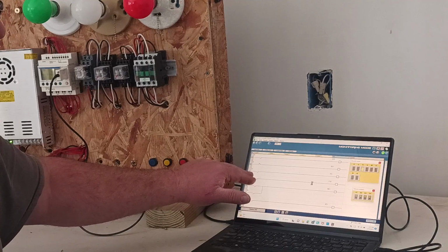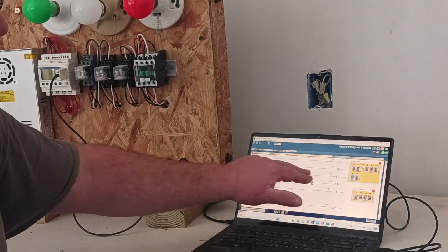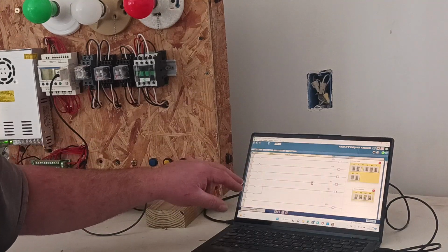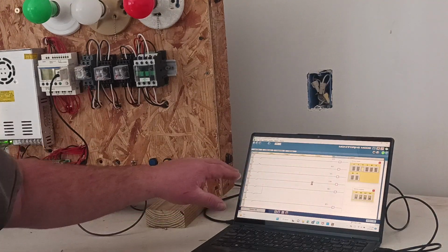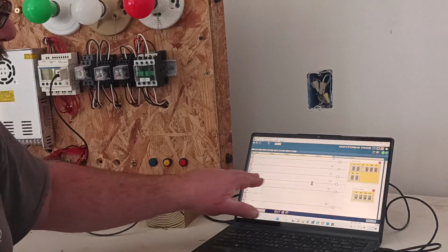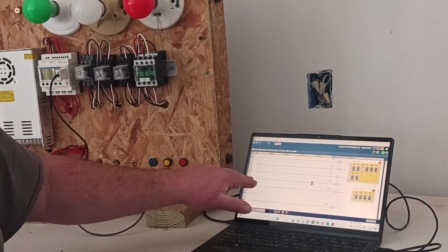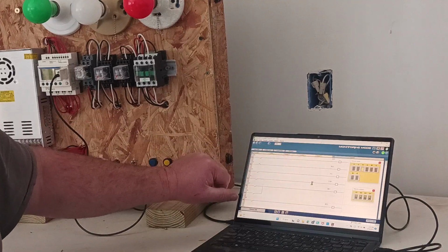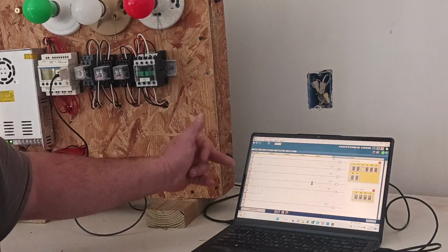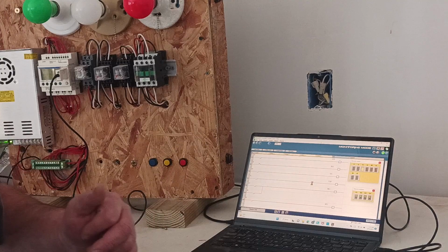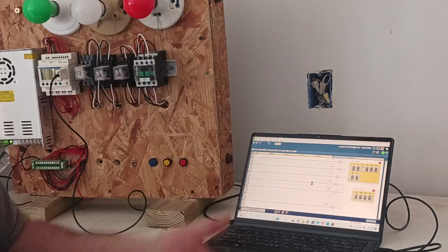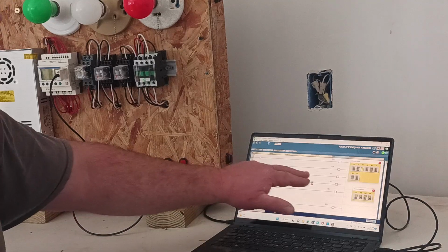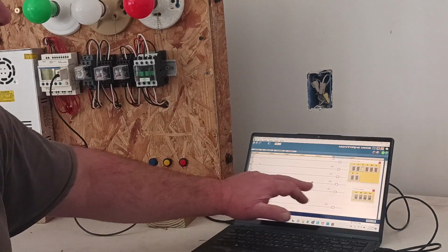You'll notice the contact for C1 goes to a timer. So I set my timer function for like 5 seconds, and my timer 1 will close, and this is an off delay timer. So once my count reaches 6, my timer will turn on. It'll engage the output, and after 5 seconds, that output will turn off. But when my counter engages my output, my counter also resets.